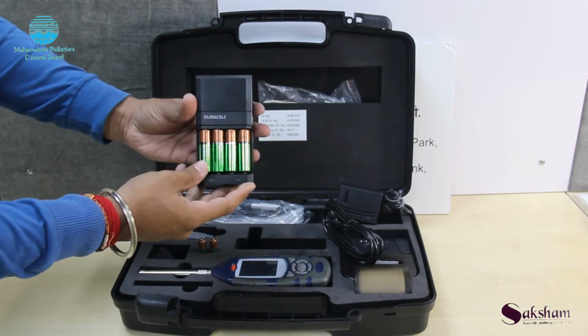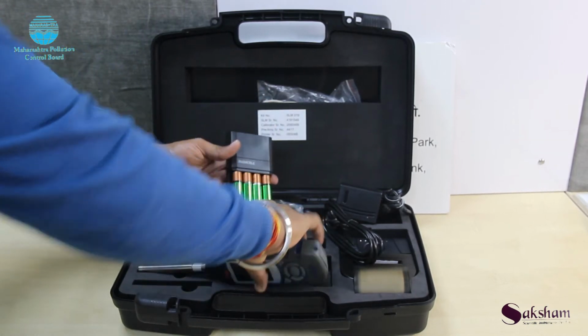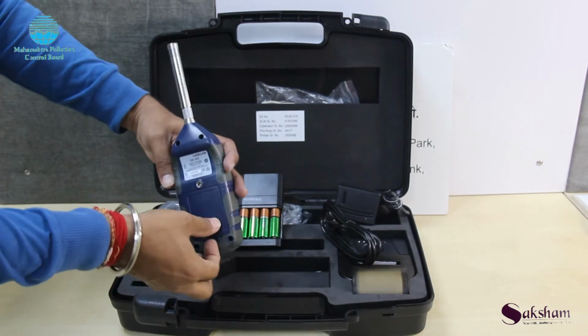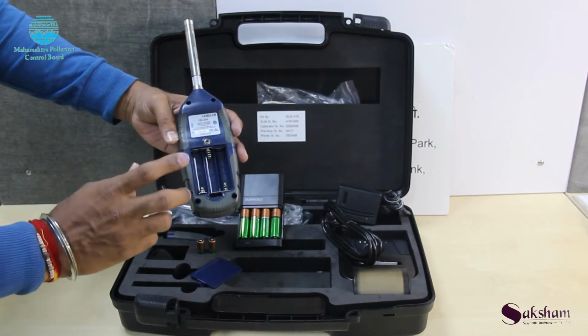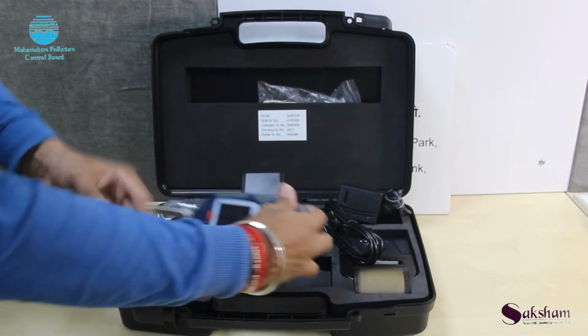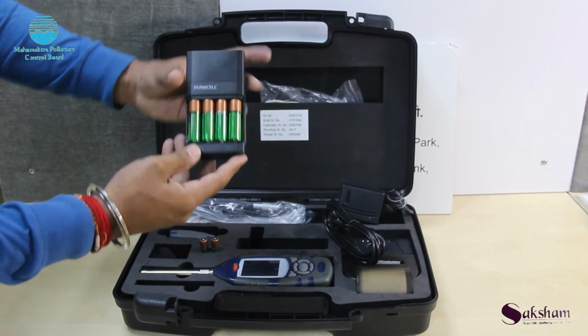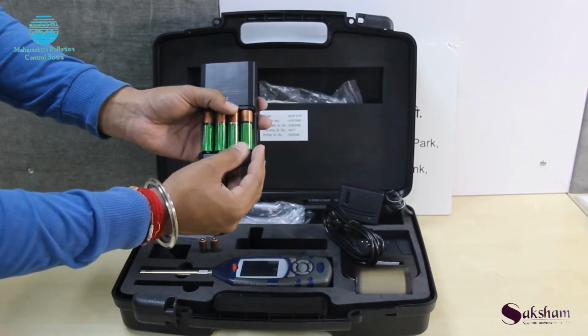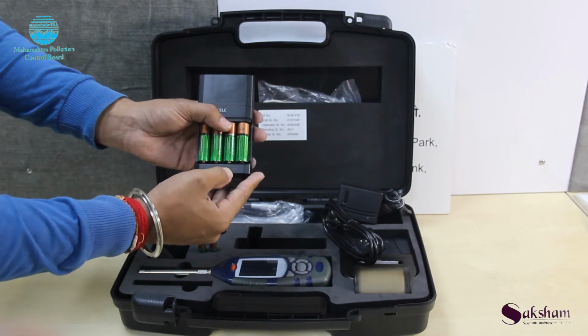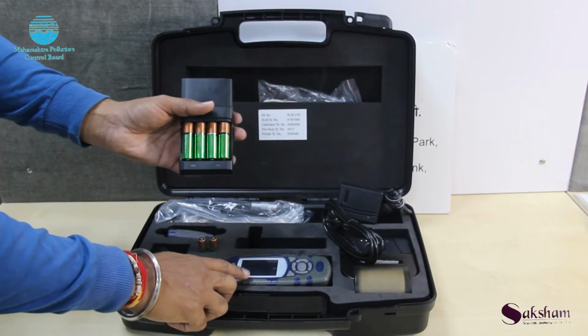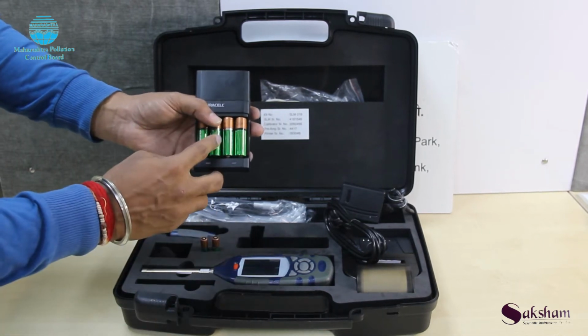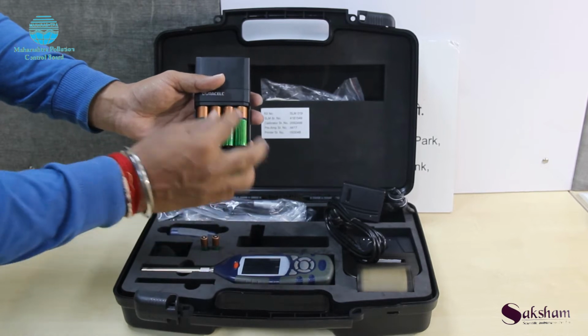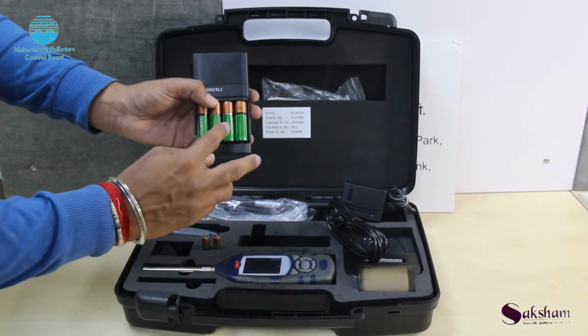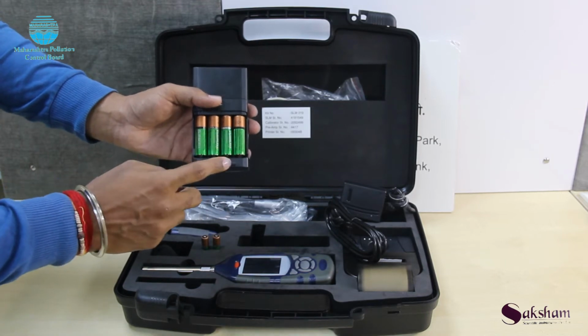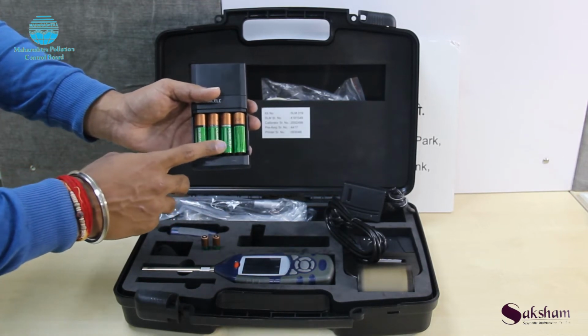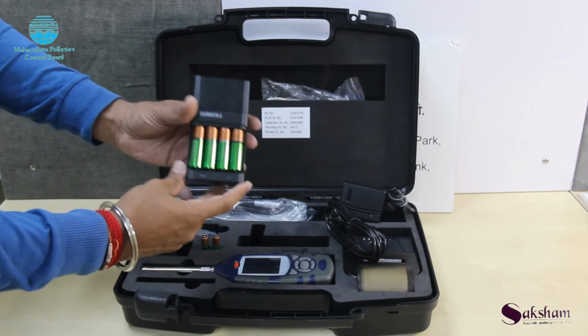these are the rechargeable batteries we need to use inside the sound level meter kit. At the time of charging, every time we need to insert 4 batteries, because these 2 batteries will make a series pair and it will charge. Generally our sound level meter kit requires 3 rechargeable batteries. If we plug in only 3 batteries, then only 2 batteries are charged and the third one is not charged. So to fully charge the 3 batteries we require all 4 batteries to be inserted in this charger.